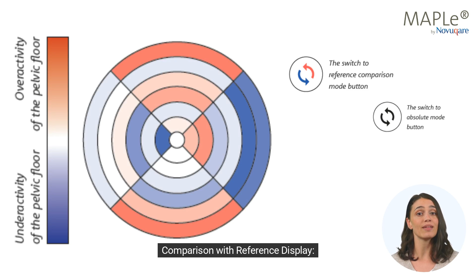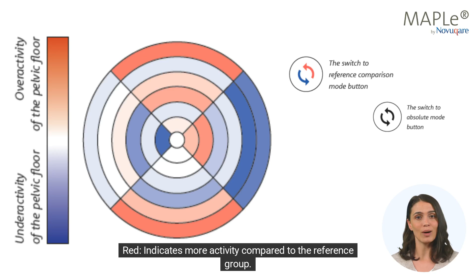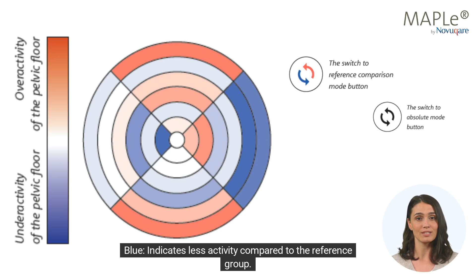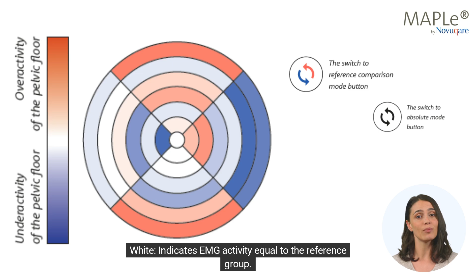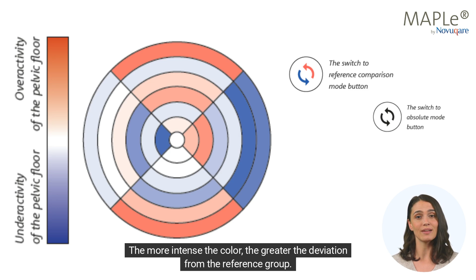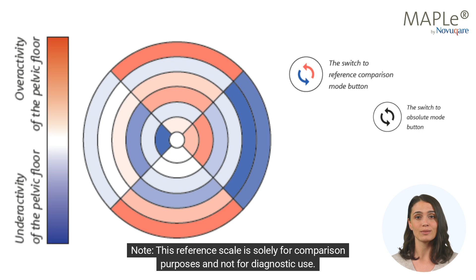Comparison with reference display. Measurements are compared to a healthy baseline from a reference group and shown in colors. Red indicates more activity compared to the reference group. Blue indicates less activity. White indicates EMG activity equal to the reference group. The more intense the color, the greater the deviation from the reference group. Note, this reference scale is solely for comparison purposes and not for diagnostic use. The absolute scale, grayscale, is best suited for that.